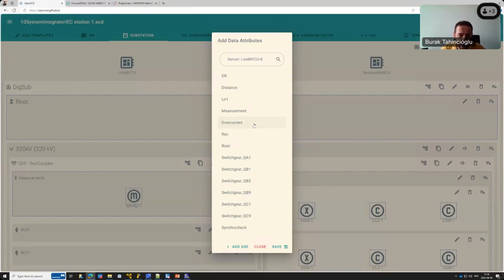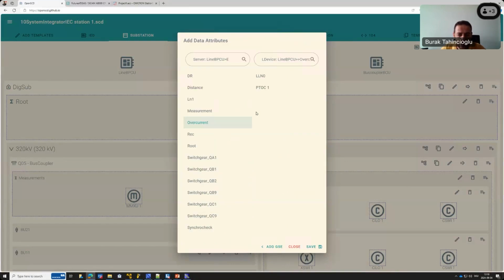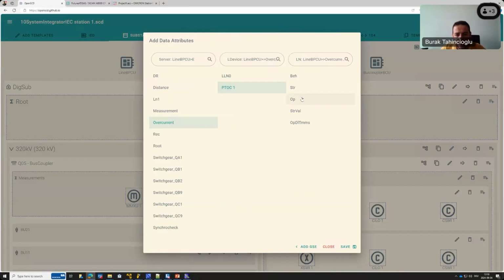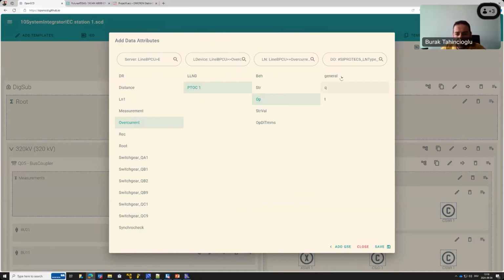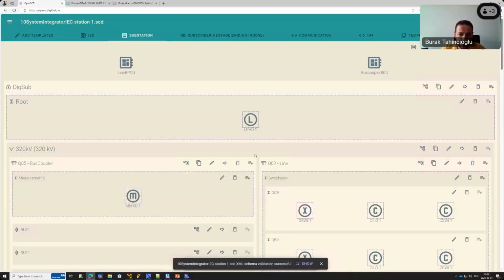So just as an example, I will communicate out the overcurrent trip. Here we have the access point, the logical device, the logical node, and I want to communicate out the operation general with the quality. Please always add the quality, not only the status data attribute. That will allow the receiver end to also understand the quality details, which may be tests, for instance, when the IED is in test mode. Okay, just as a tip also.